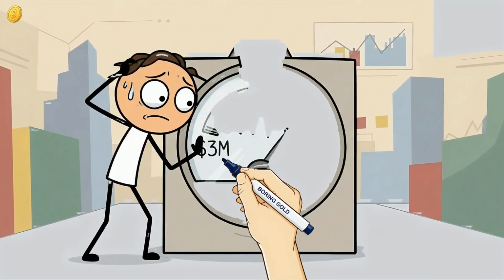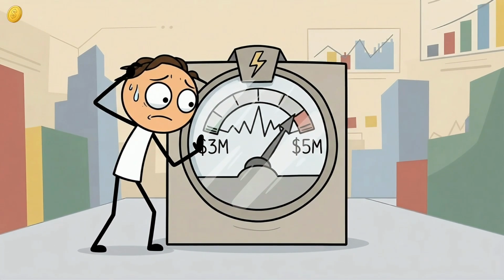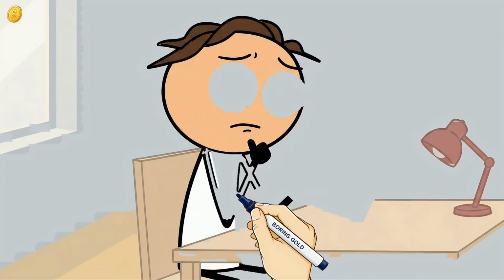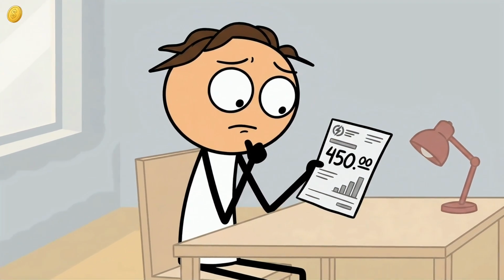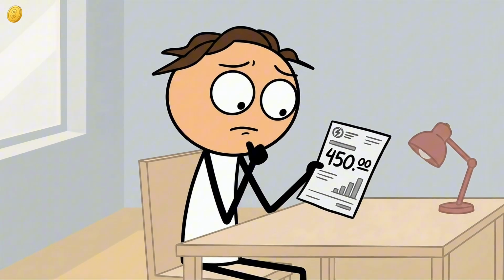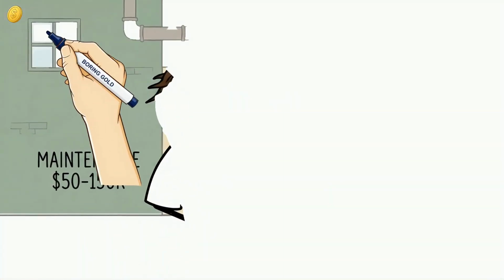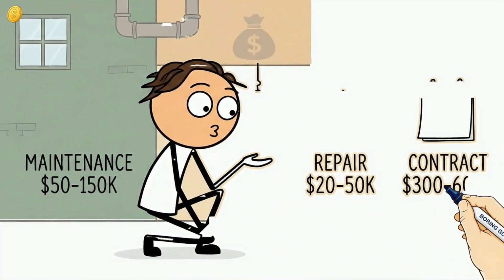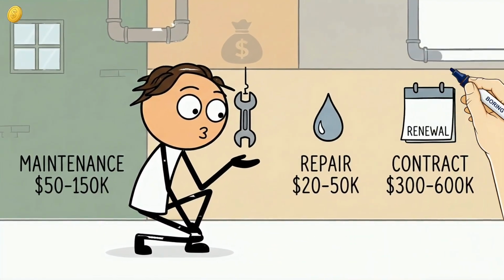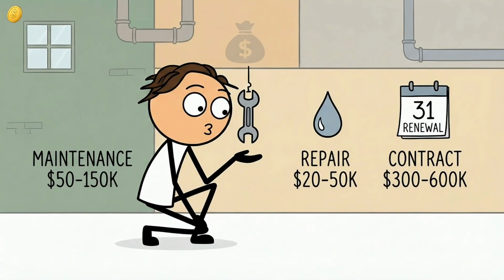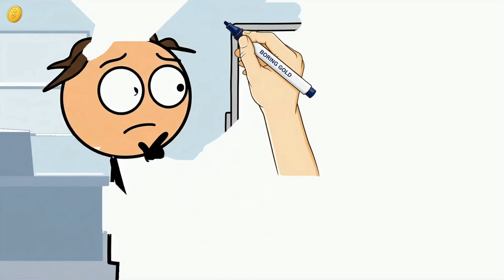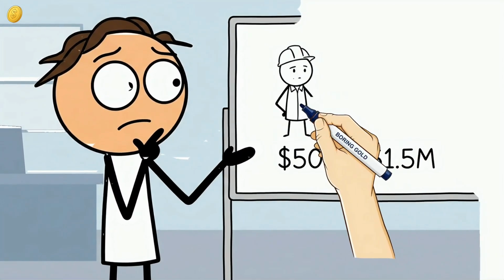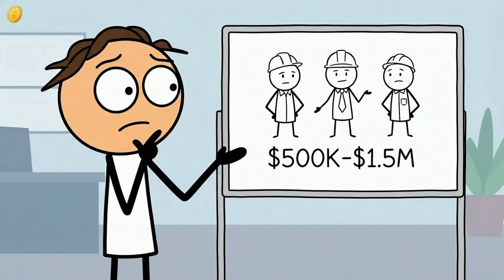Annual operating costs, electricity for compute and cooling combined, at a PUE of 1.15 with DLC, roughly $3 million to $5 million per year. Service contracts, water treatment chemicals, and periodic fluid changes, another $1.5 million to $3 million per year. Staffing with trained engineers capable of managing liquid cooling, another $500,000 to $1.5 million per year.